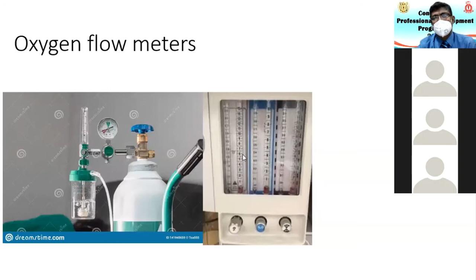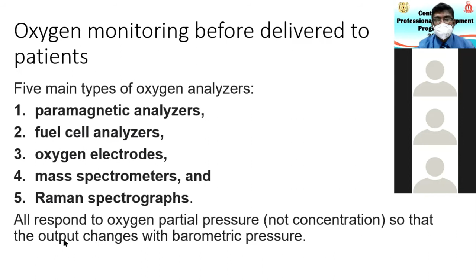I don't know whether you all know about this, but anesthetists know. These are the oxygen analyzers: paramagnetic oxygen analyzer, fuel cell oxygen analyzer, oxygen electrodes, mass spectrometer, Raman spectrograph. All of these respond to oxygen partial pressure, not concentration. Therefore, the output changes with barometric pressure.